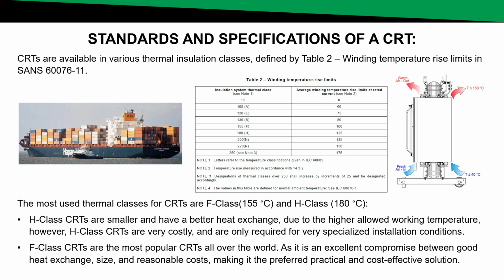Some other specifications to bear in mind when it comes to cast resin transformers are the thermal insulation classes of different cast resin and dry type transformers. These classes are listed in Table 2 in SANS 60076-11. You can see you get various different insulation system thermal classes from A to R, and then the accommodating average winding temperature rise limits for each thermal class. The most commonly found cast resin transformer insulation classes are F, which is rated 155 degrees Celsius, and H class, which is rated 180 degrees Celsius.